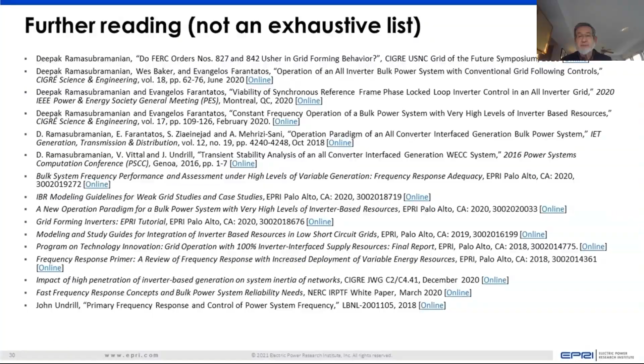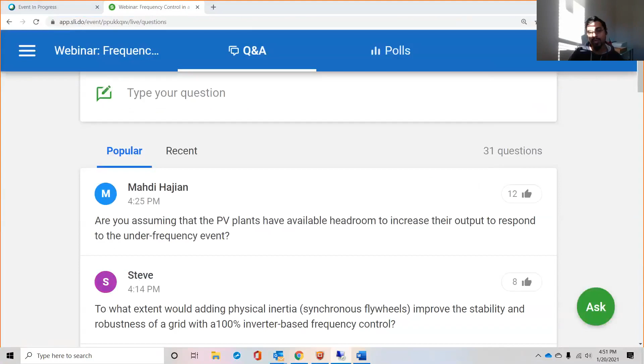Most definitely, because in a way it becomes a moot point if you are studying a 100% inverter-based resource network and all the inverters in that system do not have headroom—that becomes a moot point. So yes, definitely we assume there was headroom, but we have looked at the impact of the percentage of headroom available: if you have fewer resources or less headroom, how the frequency trajectory will change.